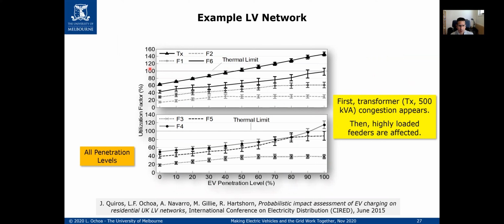What we see here, if you follow my laser, is that the thermal limit of the assets we have, the feeders and transformers, is reached at around 50% in this case for the transformer, shown by this line. For the feeders, meaning the electrical streets a single transformer supplies, it happens later, but the transformer, because it aggregates all the currents, suffers overload much earlier.